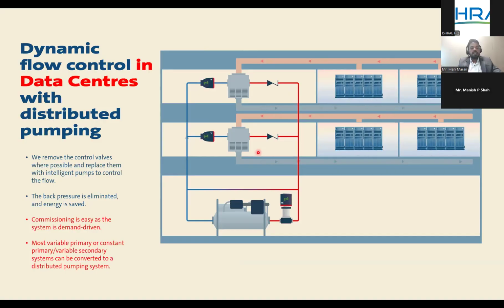And this can be very well adopted for the existing system. It can be a variable primary, or a fixed primary with variable secondary. Both systems can be retrofitted with distributed pumping, or coil pumping, or decentralized pumping, whatever term we use. It's easy to adapt in a greenfield project as well as in an existing project. The retrofit is much easier, we can really see a good payback, and it eliminates a lot of the complexity we see in today's design.